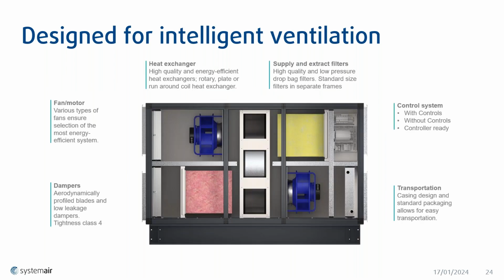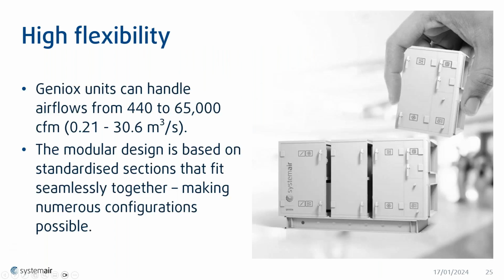Unit, as we said, it's designed for intelligent ventilation. This is a standard AHU. These would be the layouts which you would see on all normal ventilation units. So your fans, your motors, and each one of these can be individually changed, and various components can be altered within the unit to give you the actual requirement that you need. So very, very high flexibility of the units.